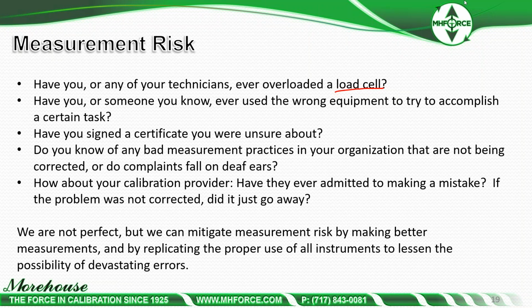No, calibration providers typically are not going to admit it. I know several that have. We've been on the course where we've had to do recalls. They're very, very painful, especially when you found it. Fortunately, the one that I remember the best, we found within a week, so we only had a week of data that we had to worry about. But it's still painful. What we found was in relation to the Agilent 3458A. We found numbers were entered wrong for a week, so we mathematically could go back and correct everything because we had records of what we did, but still not great. We're not perfect, but we can mitigate measurement risk by making better measurements and by replicating the proper use of all instruments to lessen the possibility of devastating errors.